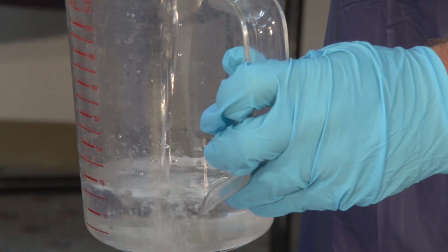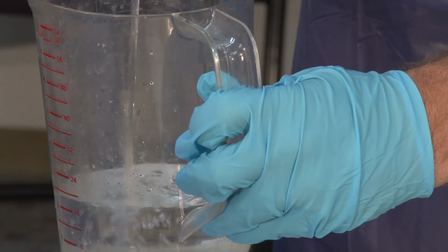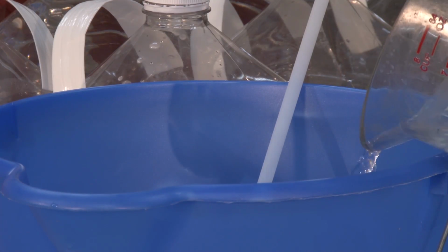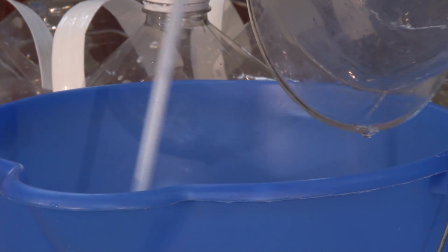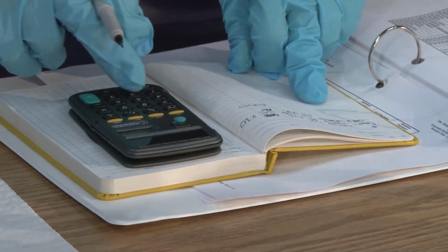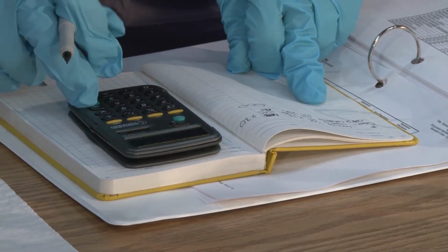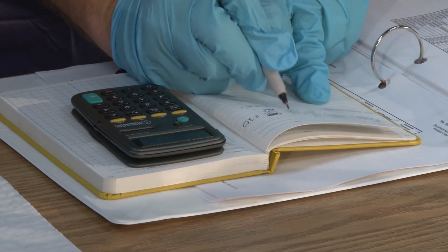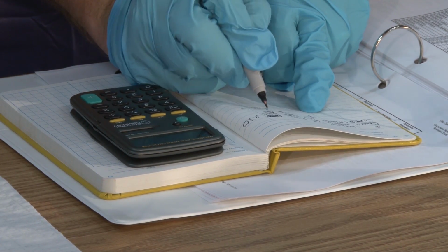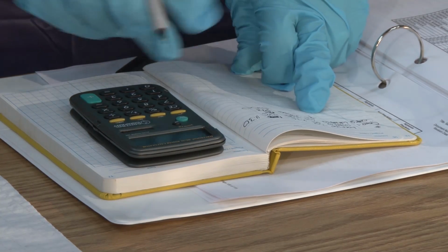Flow proportional samples require mixing measured volumes of water samples together. Remove these from each sample based on calculations using the stormwater flow data collected during the event. Calculations are required to determine the amount of water taken from each of the 9 sample containers to make up the proportional sample.